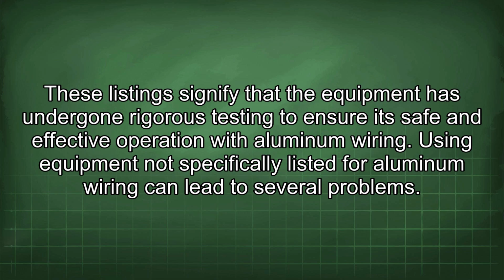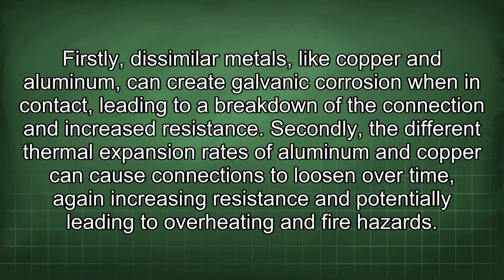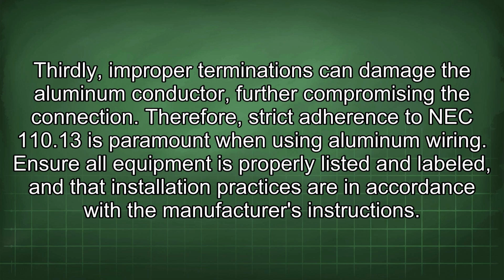Using equipment not specifically listed for aluminum wiring can lead to several problems. Firstly, dissimilar metals like copper and aluminum can create galvanic corrosion when in contact, leading to a breakdown of the connection and increased resistance. Secondly, the different thermal expansion rates of aluminum and copper can cause connections to loosen over time, again increasing resistance and potentially leading to overheating and fire hazards. Thirdly, improper terminations can damage the aluminum conductor, further compromising the connection. Therefore, strict adherence to NEC 110.13 is paramount when using aluminum wiring. Ensure all equipment is properly listed and labeled, and that installation practices are in accordance with the manufacturer's instructions.